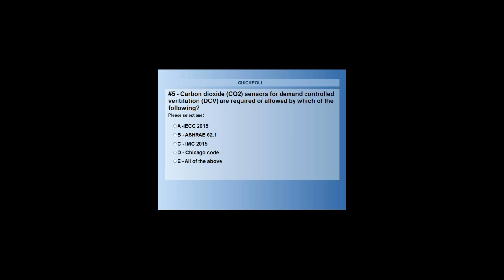However, if you were to do a LEED project in the City of Chicago, you would have to comply with both. The city's code has to be complied with, obviously, and then for LEED, because 62.1 is a prerequisite to even get a LEED building built, you have to comply with that. So you would look at the two tables, figure out which one requires more outside air than the other, and whichever one is the higher number, you would have to use. Generally, my bet is that in most projects, it's probably going to be the Chicago ventilation code. That'll be the higher number.